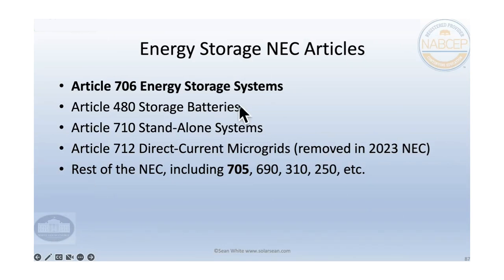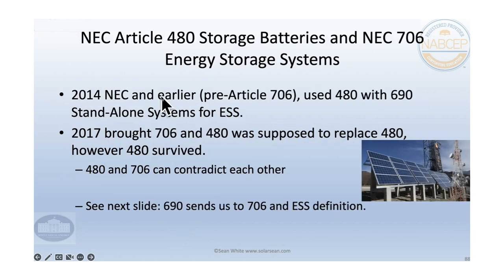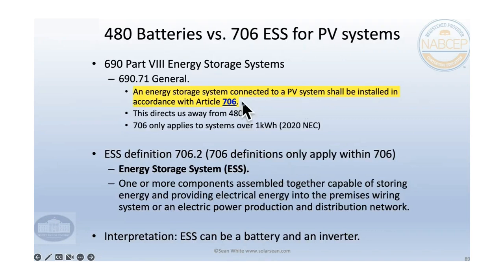So here are different energy storage articles that we're going to talk about. We're not going to talk about 712. In fact, in the 2023 NEC, they took 712 and stuck it into 705 interconnections where AC microgrids were. But we are going to mostly talk about 706 today when we're talking about the code for energy storage systems. And there are all these different reasons why you shouldn't go to 480. One of the easy ones is if you're doing a PV system, 690 tells you not to use 480 for energy storage. It was the intention when they made Article 706 in the 2017 NEC to get rid of 480. And then at the last minute, the telecom people got them to keep 480, because telecom people don't want to have many rules. They will just put a bunch of batteries there, even without DC disconnects and things like that. So here in 690, it says use 706.